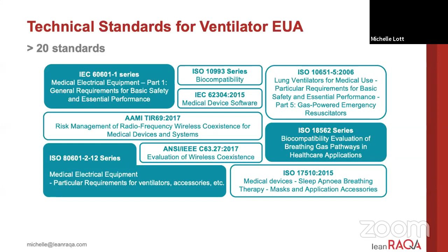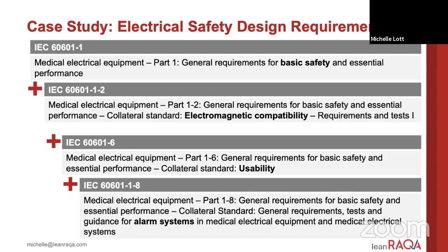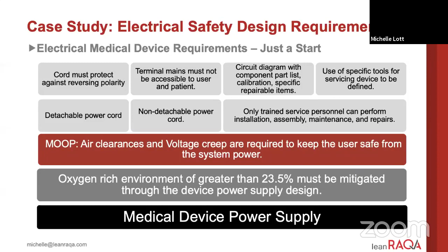We're going to do a quick case study on electrical safety design requirements. No matter what kind of medical device you're designing, if it has electrical properties, you have at minimum these sets of standards for basic electrical safety, electromagnetic compatibility, usability, and alarm settings. And if we quickly look at a specific example in these technical standards, just for the medical device power supply, you have to get into what type of environment it's used in. That type of environment dictates if you have to have air clearances and voltage creep. Then it gets down into very specific deliverables of your device design with power cords, and what type of personnel are going to be installing your device. And that's just one specific example.